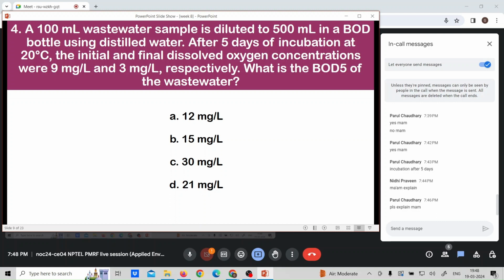When you are coming to your dissolved oxygen calculation, you have done a titration experiment basically. I hope you understand. So what you do is you just have a formula: dissolved oxygen is equal to volume of the titrant, or the sodium thiosulfate solution that you used, into its normality, into 8000, divided by sample volume. So this is how you will find out this DO.